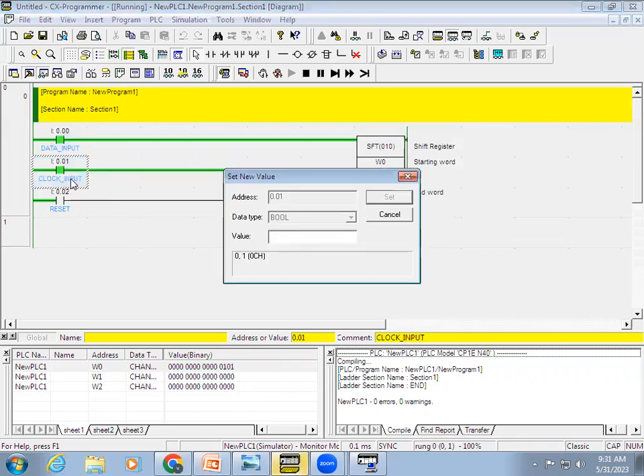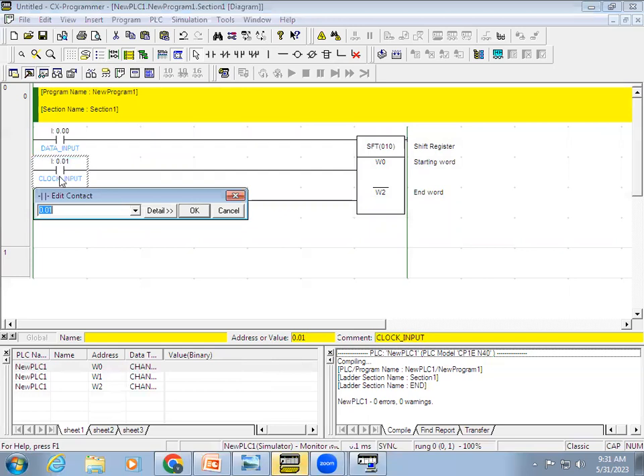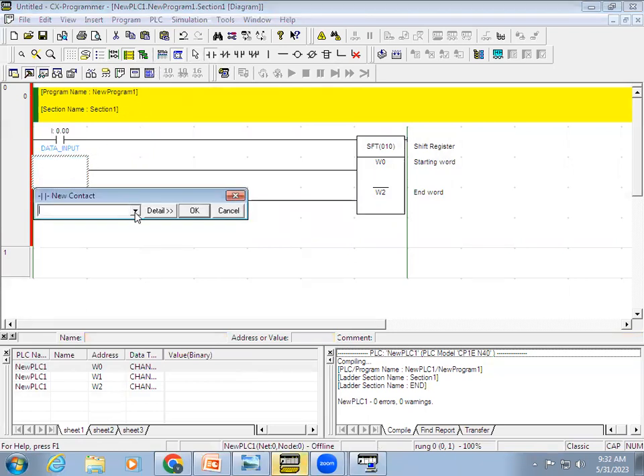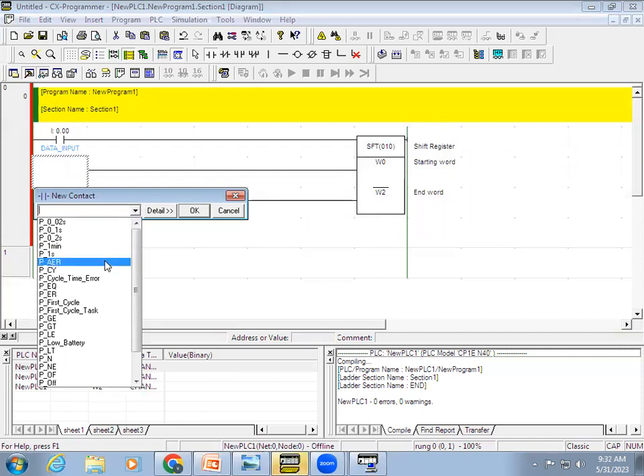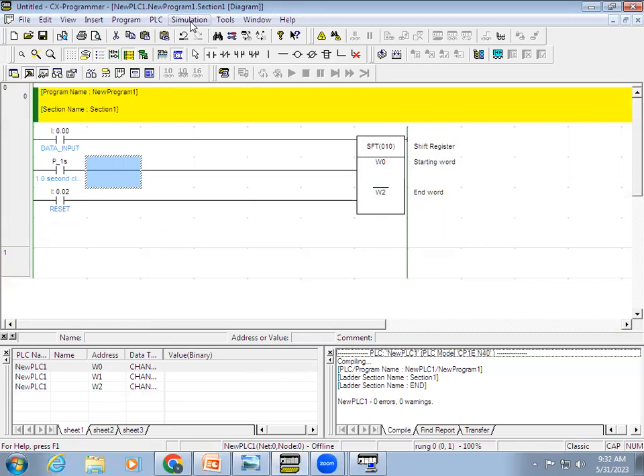The shifting will continue across all three sets of 16 bits. Since I can't manually toggle on/off continuously, I'll turn off simulation mode and instead of using a switch I'll assign an auxiliary relay contact — P_1second — which gives a pulse every one second. That means every second it gives a trigger signal, and whatever data is present in the data input, true or false, it will keep on moving. Now let's go back to simulation to check this.